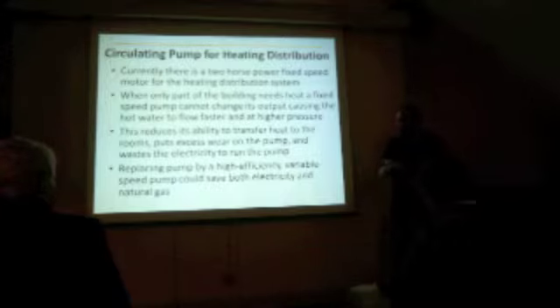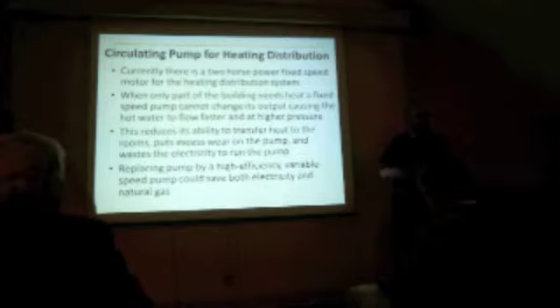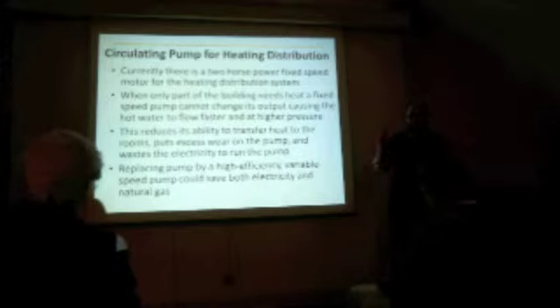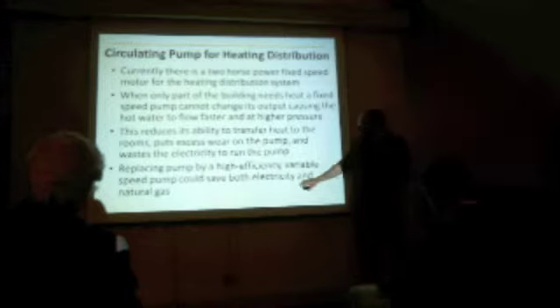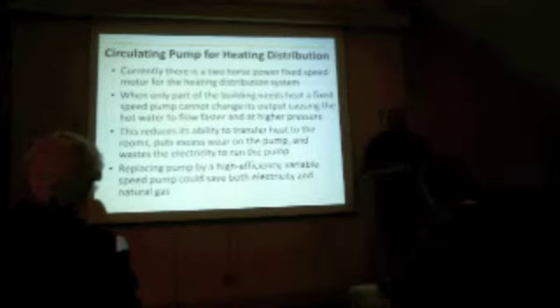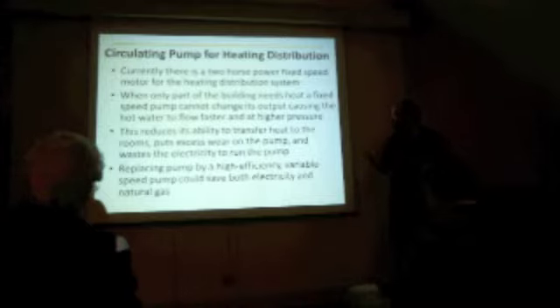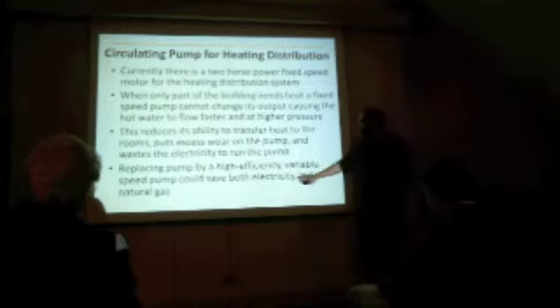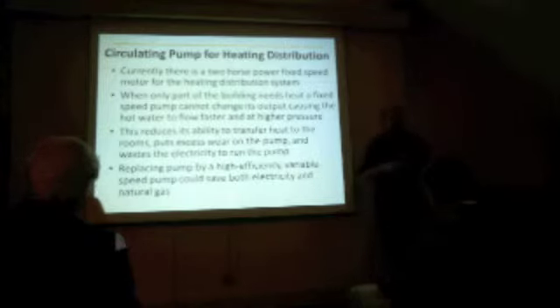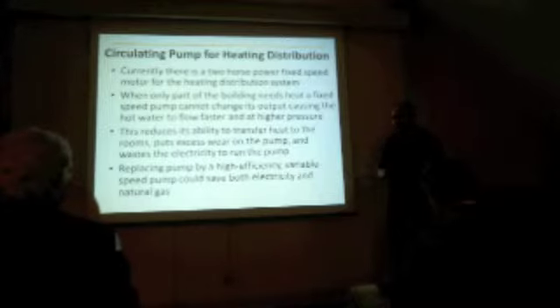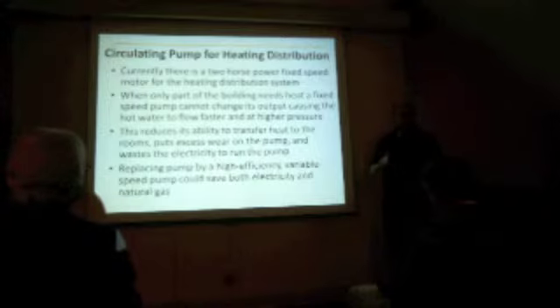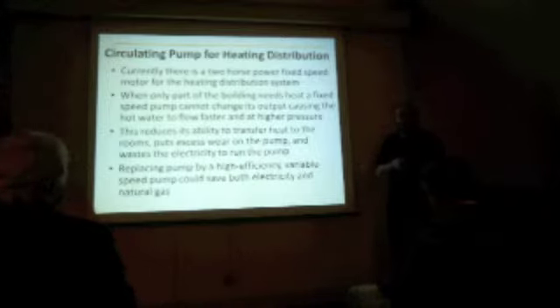Pumps are outside my expertise, but when you look at it, they say cutting the power by a factor of 2 can increase the life by a factor of 7 because you're running at a much lower power. So there are quite a few companies that sell what are called variable frequency drives that can connect to the motors and control them to make variable speed pumps for these kinds of heating systems. These usually have pretty good paybacks because the energy reductions are so dramatic compared to just running that pump on and off. And so this would be another one that I think would be worth looking at as a potentially simple solution. A quick back of the envelope, you could save maybe as much as 1,000 kilowatt hours, depending on the occupancy of the spaces.